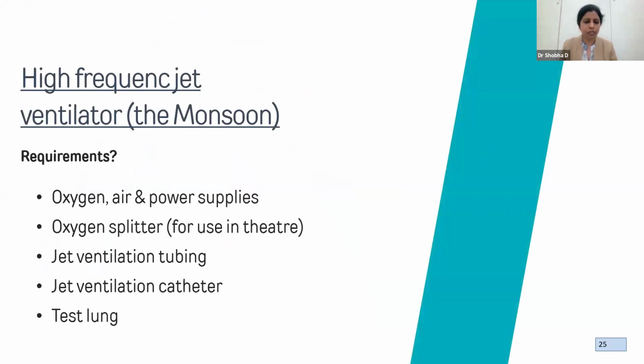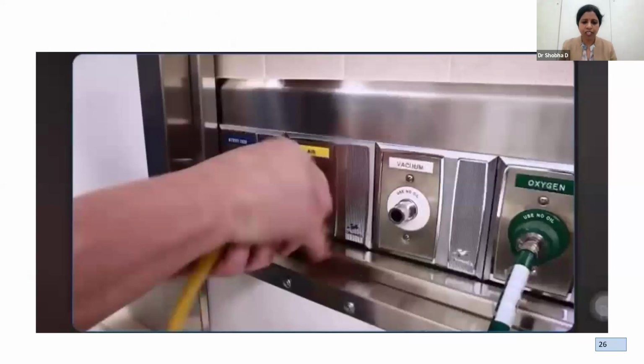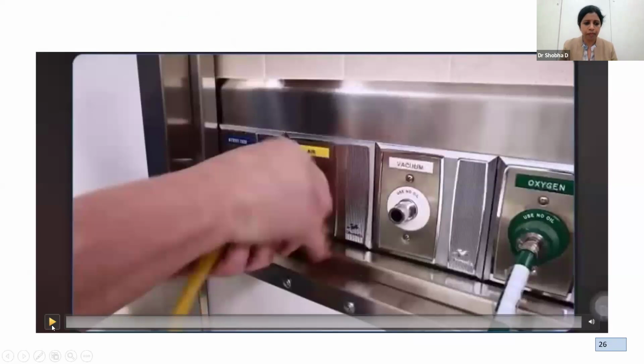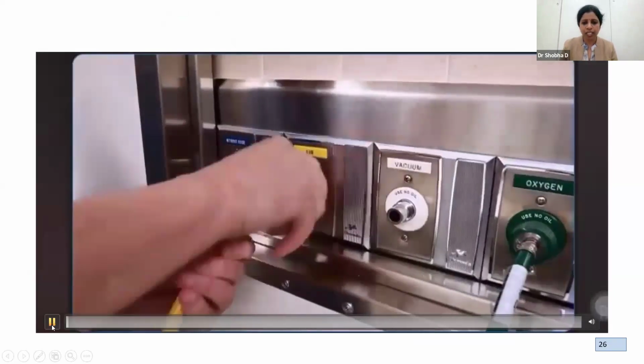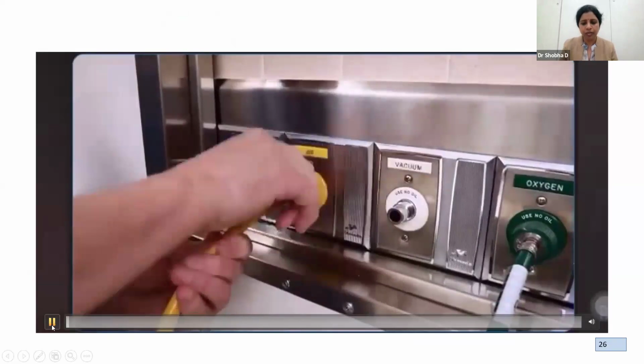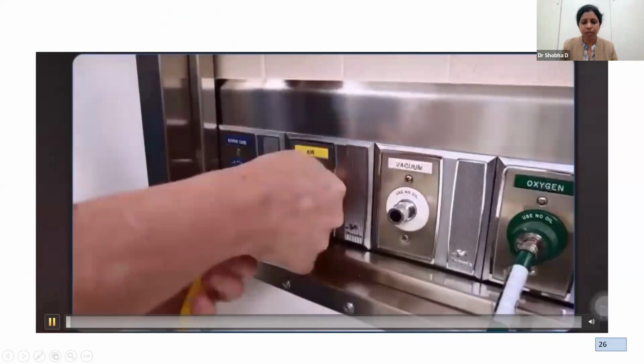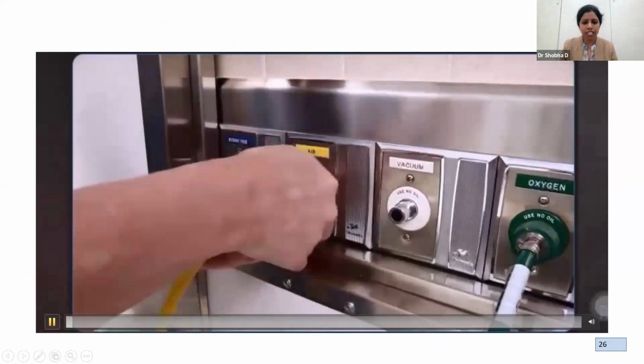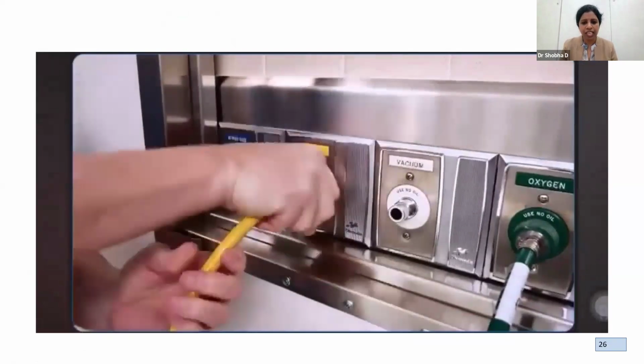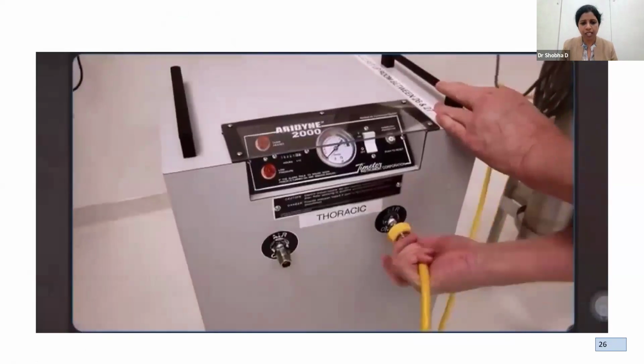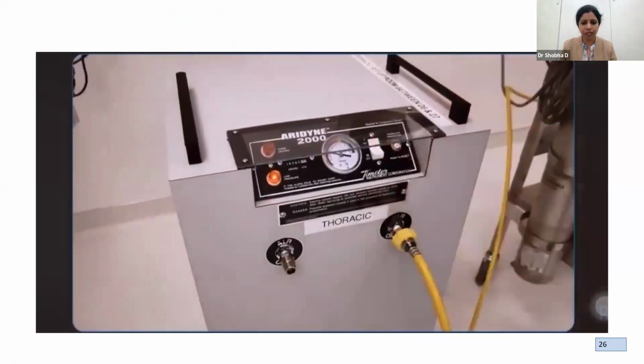To quote an example, what if the ventilator is a Monsoon? What do we need here? We need oxygen, air, the power supply, the oxygen splitter, jet ventilation tubing, jet ventilation catheter, and the test lung, basically for the safety test. Here there is a clip which shows how to set up the ventilator. The air and the oxygen supply are connected to the pipeline. If there is no air, you can use an external compressor. Use sterile water for the humidification. There are 2 tubings. The blue is for the jet ventilation and the red is for the pressure monitoring, and these are connected by the Luer lock mechanism to the test lung.